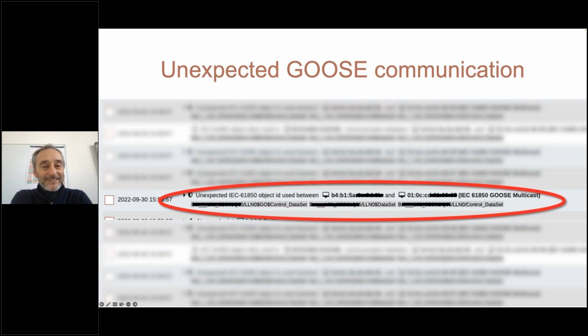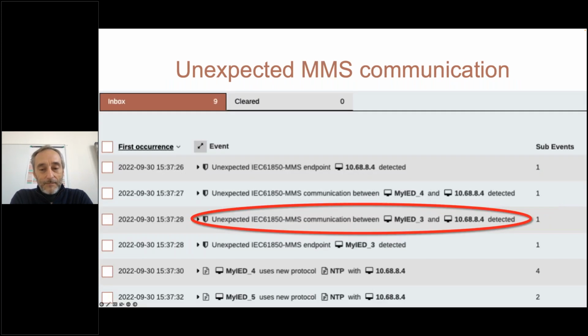This is another example, with MMS. This is test data, so it's less redacted. You can see this IED and IP address aren't supposed to talk MMS, or rather, the server and client aren't defined as MMS endpoints in the SCD. So again, this is an anomaly.